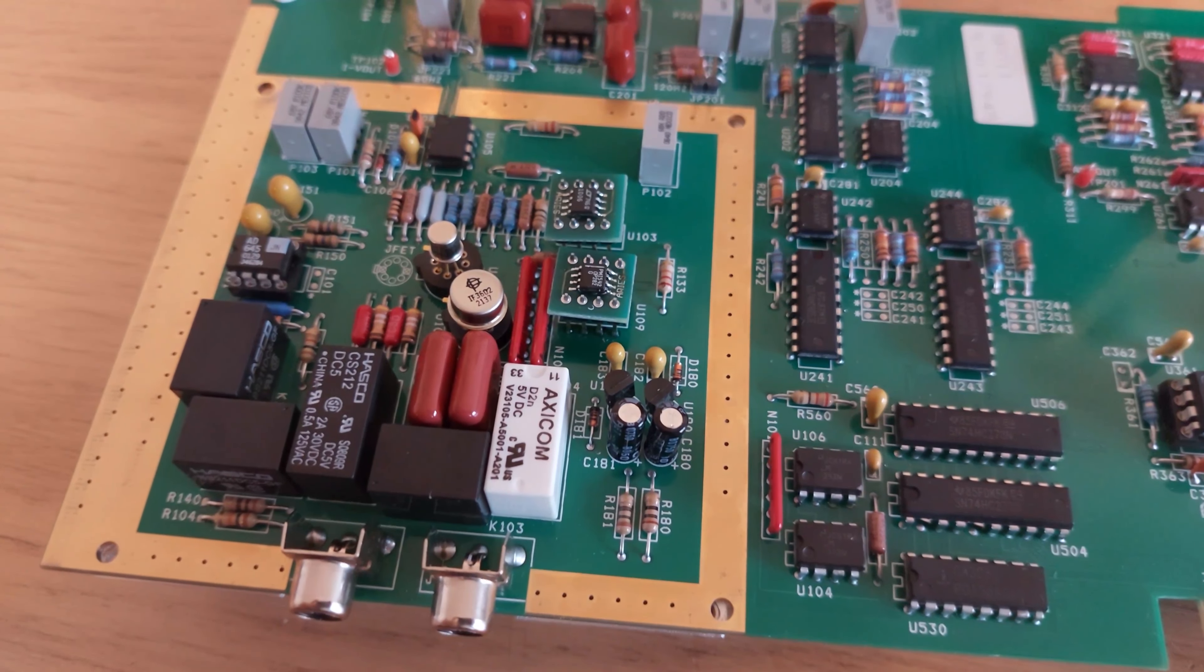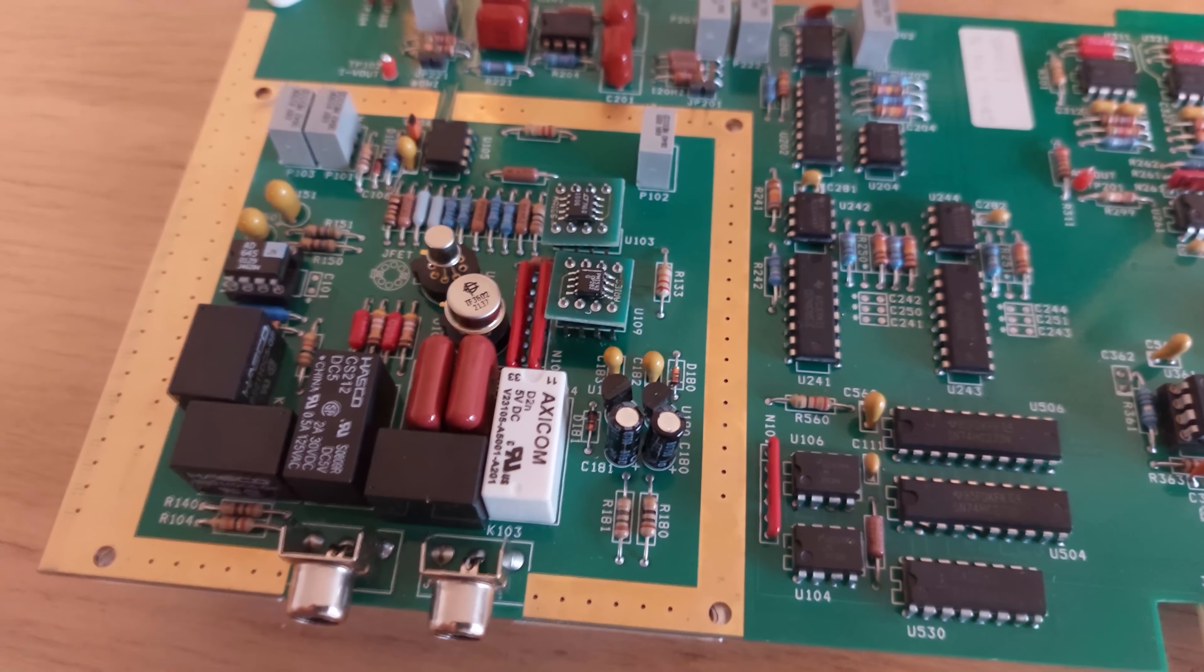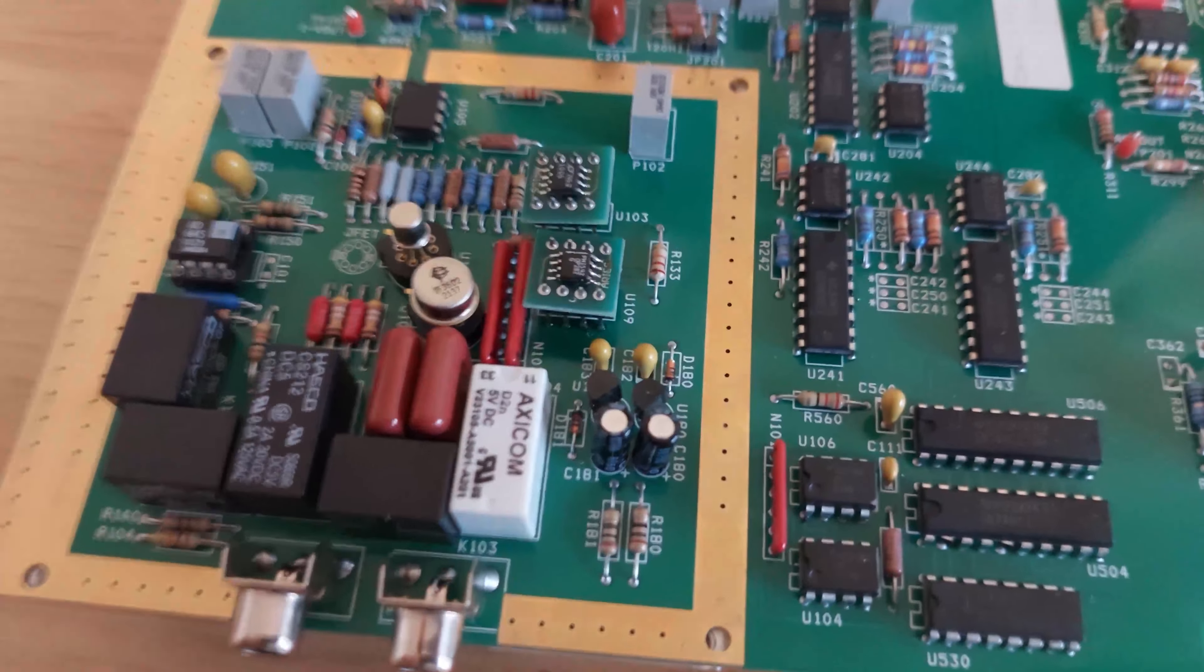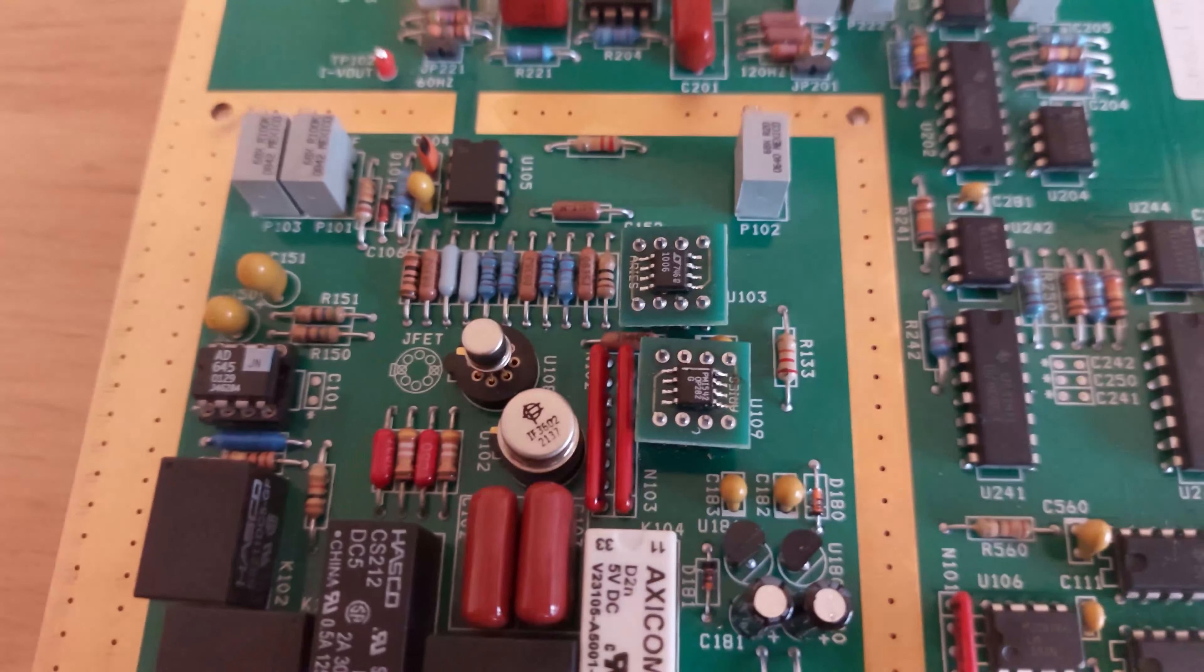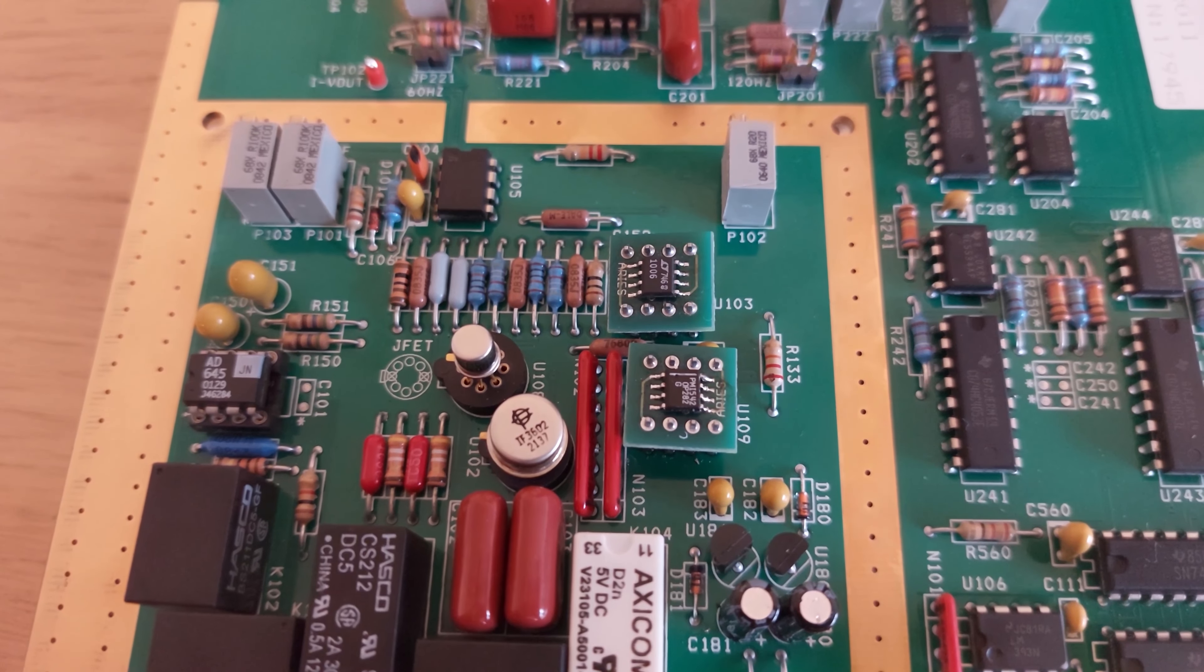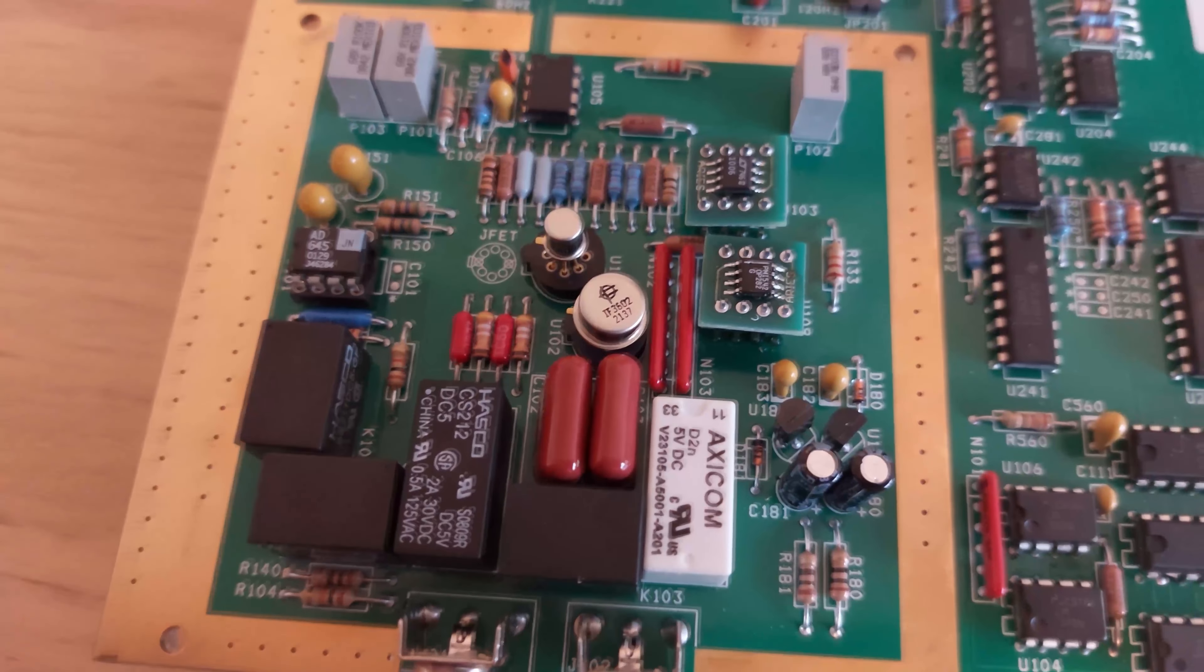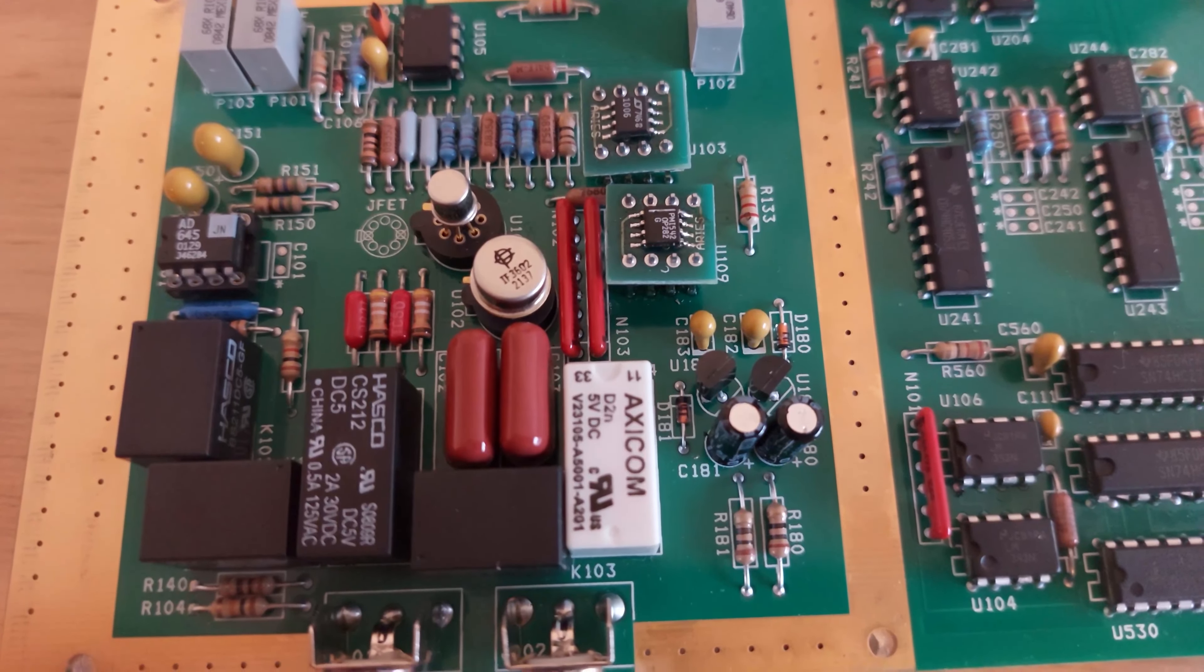If we take the shielded can out, you'll be able to see the main source of problem of this instrument, which is the front end. If you look closely, you're going to see that there are a few non-standard parts here. In my quest of repairing this device, I've actually changed a few parts that were actually good—two op-amps mainly.